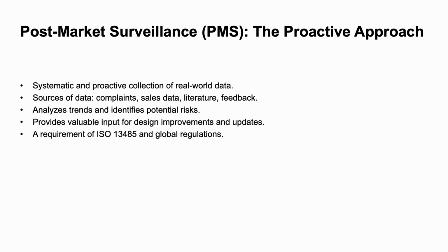It is a systematic process for gathering and analyzing data about a medical device once it is on the market. Unlike the reactive nature of medical device reporting, which only captures serious adverse events, PMS is designed to identify subtle trends and potential risks before they escalate into serious issues. A manufacturer's PMS system should collect data from a variety of sources. This can include customer complaints, sales and service records, and information from published scientific literature.